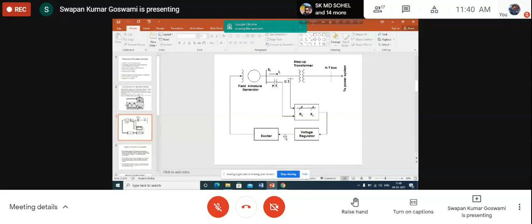Now, what are the types of excitation system? The types of excitation system are basically decided by the type of the exciter. It may be a DC exciter, a DC generator may be used, and the name will be DC excitation system. The exciter itself may be an AC generator. Then the name is AC excitation system, or it may be a static excitation system, because in that case the generator will be self-excited. And why is it called static? Because the generated voltage is rectified in the rectifier. That's why it is static. Static means, on electronic circuits, we call these static devices. That's why it is called the static excitation system.